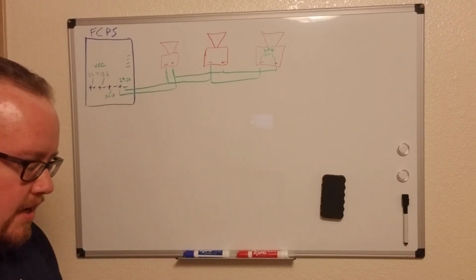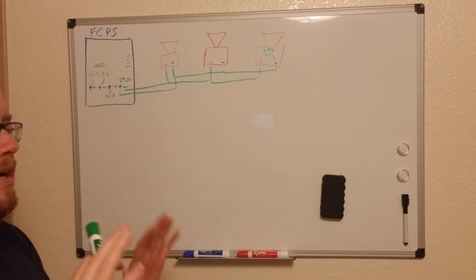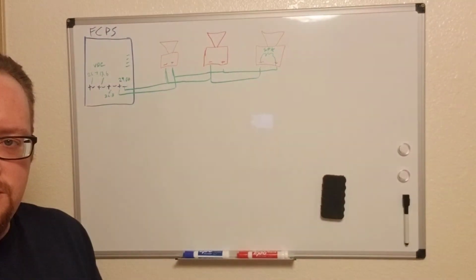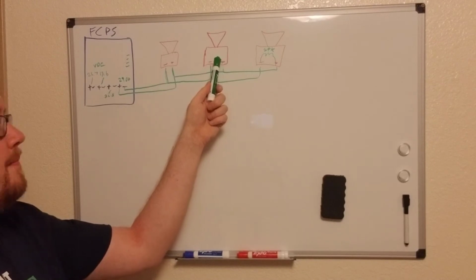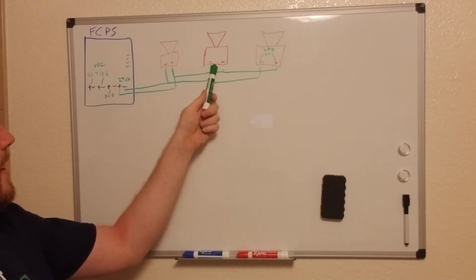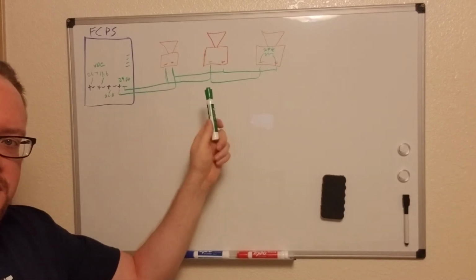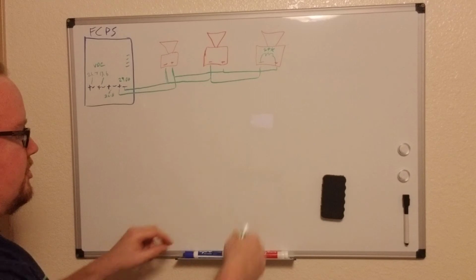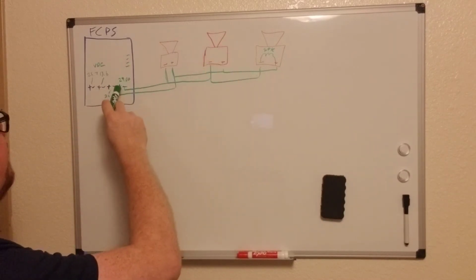and we're going to see that voltage go up on an open circuit. And so here's where this becomes really a huge time saver and makes your troubleshooting so much easier, is when you go out in the field and you pull this horn strobe off the wall, you're going to see the wires on the back. You're going to stick your meter right on those wires while they're still hooked up, and you put your leads right there and you see, oh, look, there's 29 volts.